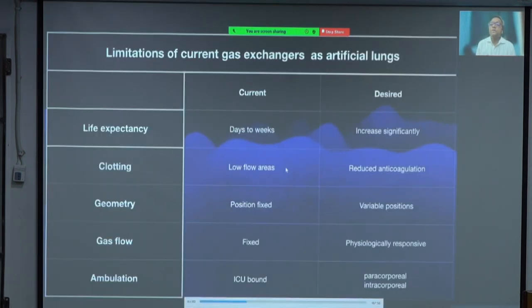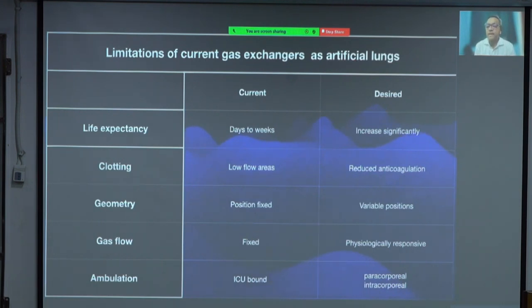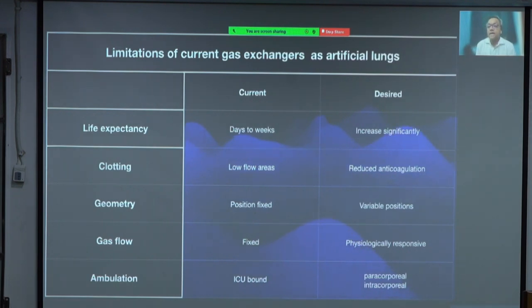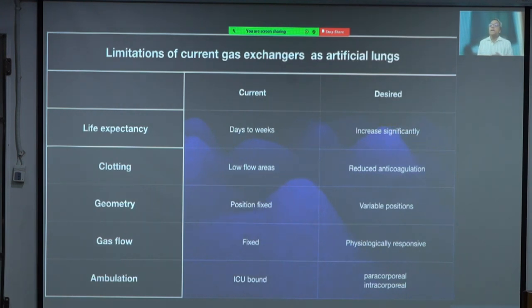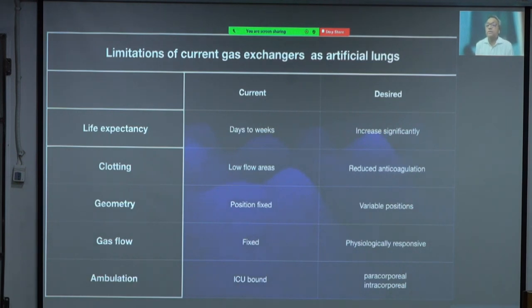If we want to produce a wish list for an artificial lung, the life expectancy of the gas exchange membrane has to increase significantly — it is currently days or weeks, sometimes pushed to months, but for long-term support as a lung assist device it must increase significantly. There are areas of maldistribution of blood in the chamber leading to clotting, and because of the synthetic interface we have to give anticoagulation, which we want to reduce significantly because one of the side effects is bleeding.